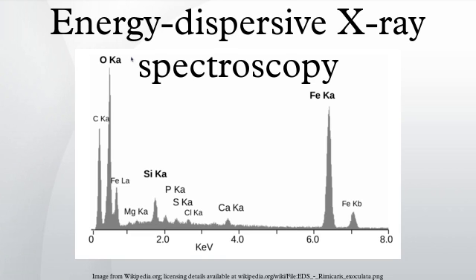There is a trend towards a newer EDS detector called the silicon drift detector (SDD). The SDD consists of a high-resistivity silicon chip where electrons are driven to a small collecting anode. The advantage lies in the extremely low capacitance of this anode, thereby utilizing shorter processing times and allowing very high throughput. Benefits of the SDD include high count rates and processing, better resolution than traditional Si detectors at high count rates, lower dead time, faster analytical capabilities, and more precise X-ray maps or particle data collected in seconds, as well as the ability to be stored and operated at relatively high temperatures, eliminating the need for liquid nitrogen cooling.